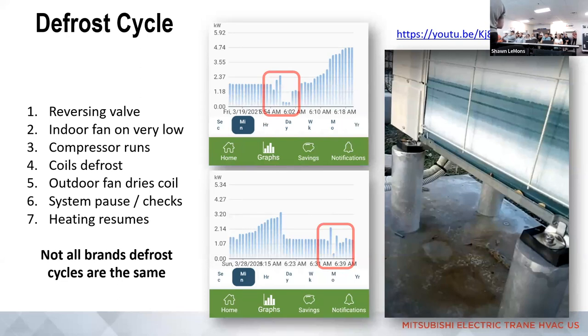Really all it's showing is that yes, defrost happens in the winter, and it may or may not slow the ramp up or recycling, but the system has its own logic—it goes into defrost when it needs to and then stops. It's not a timed thing, not happening every 20 minutes or every hour on the hour. It happens when the system can tell it needs to.